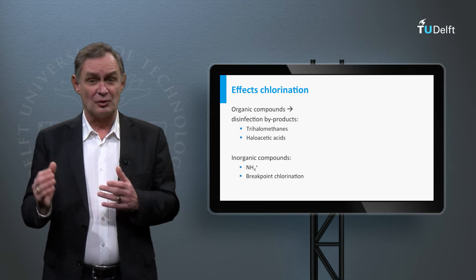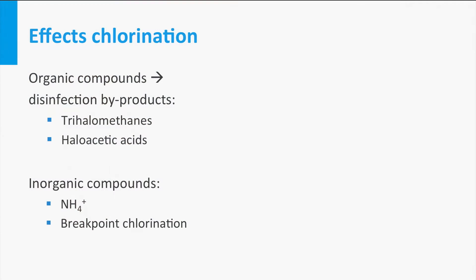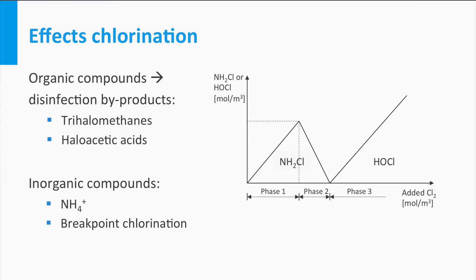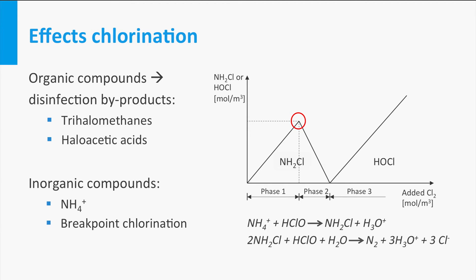This phenomenon is called breakpoint chlorination, shown in this figure. At this point, all the ammonium is converted into monochloramine via the reaction shown on the slide. The free chlorine is thus converted to what we call combined chlorine. When additional hypochlorous acid is added, it reacts with the monochloramine, and at the breakpoint, the reaction is over and all the ammonium is removed.